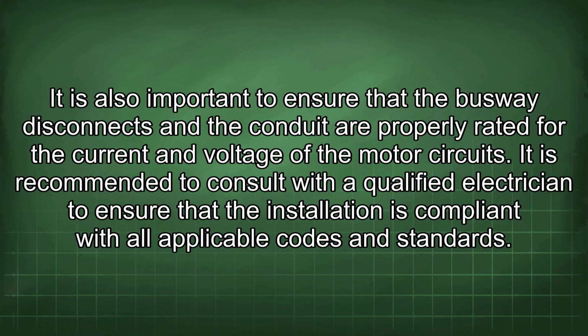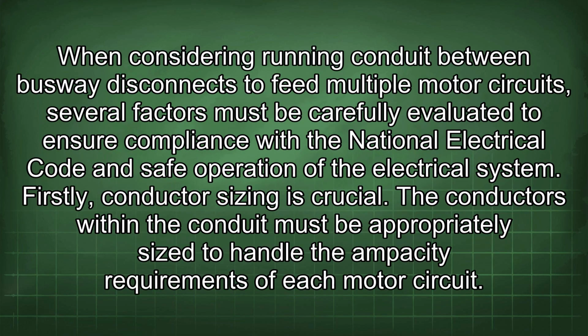When considering running conduit between busway disconnects to feed multiple motor circuits, several factors must be carefully evaluated to ensure compliance with the National Electrical Code and safe operation of the electrical system. Firstly, conductor sizing is crucial. The conductors within the conduit must be appropriately sized to handle the ampacity requirements of each motor circuit.